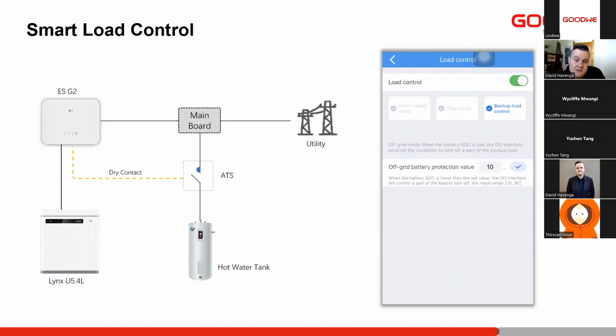With all of our hybrids, not just the ESG2, so all of our newer hybrids, have the smart load control integrated that you can control from the SolarGo application. So you can connect a relay to it. It's got a dry contact that you can switch based on backup load. So if you want to switch a load into the backup of the inverter, if you want to switch certain loads on at certain times, or if you just want a power switch mode. So once you reach X amount of PV production, switch on certain loads. This is very nice for off-grid situations to make sure you charge your battery full. Once we've got X amount of solar, then we can switch on a load to the backup. And once the batteries start draining to a certain level, we can switch that load off again.